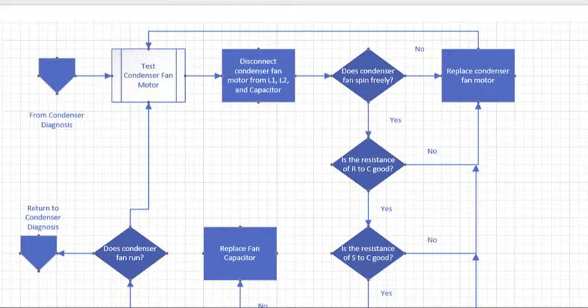To test the condenser fan motor properly, what we want to do is disconnect the condenser motor from L1, L2, and the capacitor. If you do that as your first step, you're never going to forget to do it as you continue on through the testing.